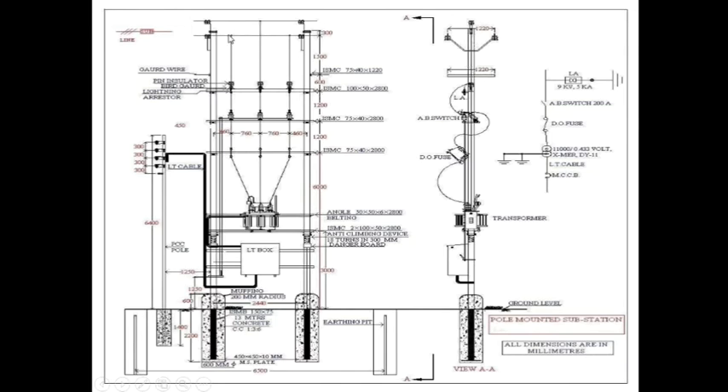Now, this is the pole-mounted substation. Here, 11 kV comes to the LA, and then to the AB switch, then to the D.O. fuse, then to the transformer HT side, then from LT side to the distribution box, then outgoing to consumers.